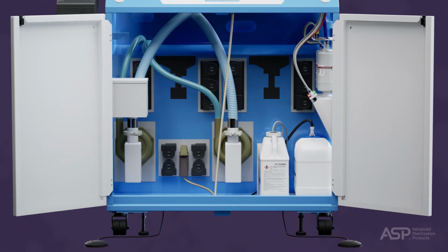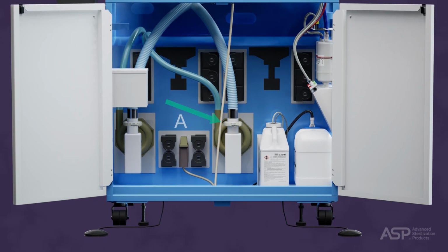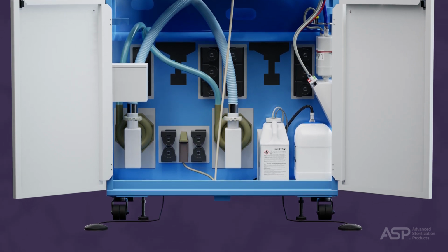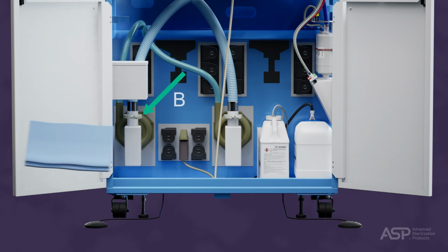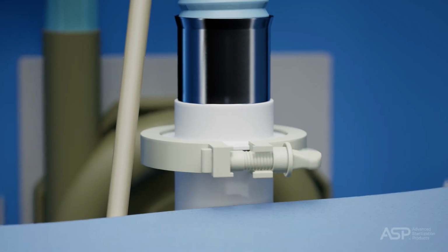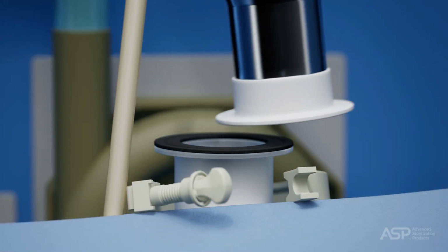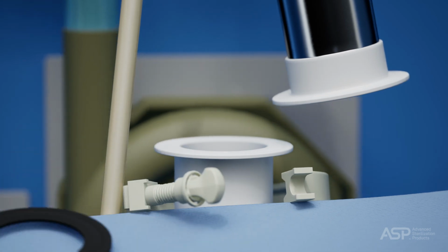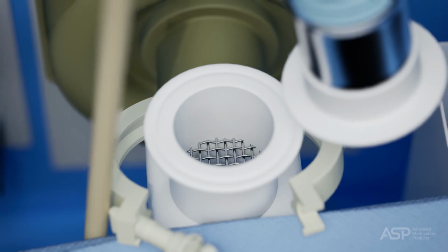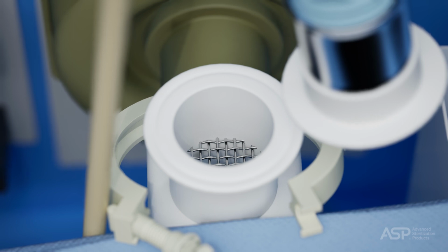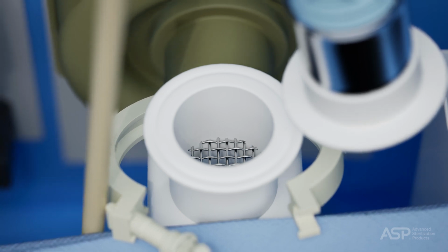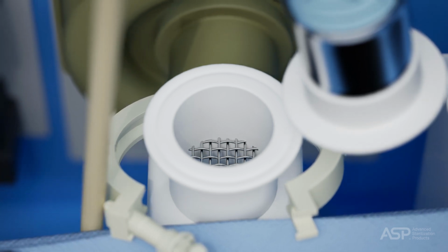The manifold serving the left A basin is located on the right. The manifold serving the right B basin is on the left. Unfasten the clamp and remove it. Remove the O-ring and save these items for later use. The coarse screen is inside this base unit. You should be able to see the coarse screen and remove anything that may be blocking the flow of liquids.